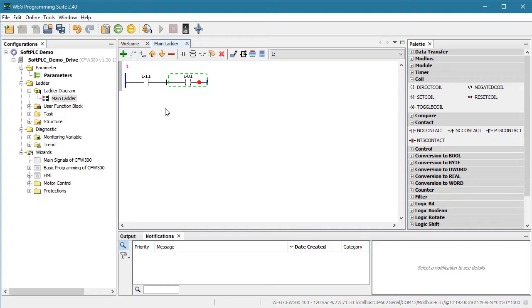One of the cool things about the WEG drive is that the digital inputs aren't limited. In some drives, if you use the digital input in a Soft PLC then you can't use it in the drive and vice versa. So the good news is the WEG drives don't limit you like that. The bad news is you need to be extra careful because the drive may be using a digital input that you are also using in the Soft PLC.